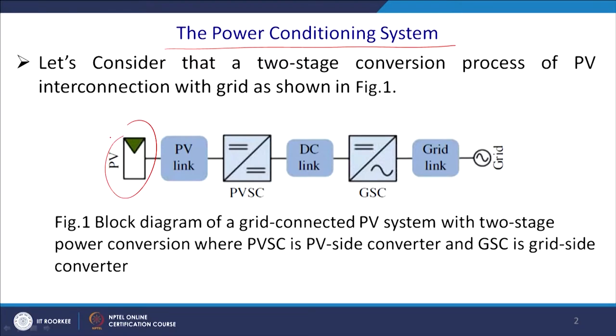You have a PV source and a PV link that will transmit the power, and ultimately you will track the maximum power point. For this reason you have a DC-to-DC converter. One DC-to-DC converter will track the MPPT, another DC-to-DC converter will give you the desired voltage level, and thus you come to the DC link, which is an entry point.